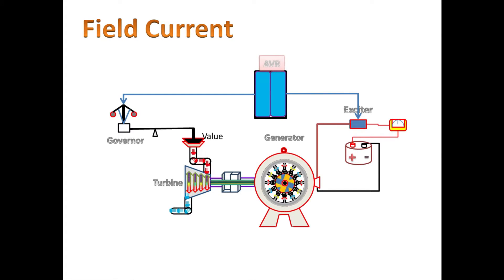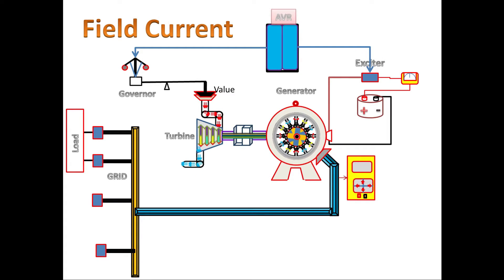Second method is by measuring reactive power of the generator, we can able to detect the loss of field protection. During normal running condition, the VAR is exported from the generator, but mainly during under excitation problem, the VAR is imported from the grid to generator.